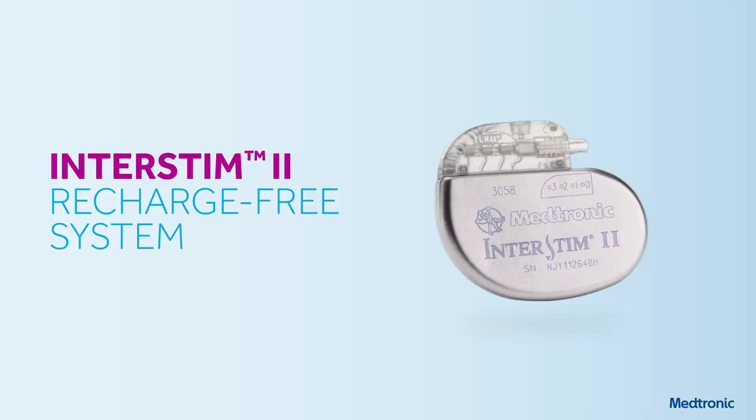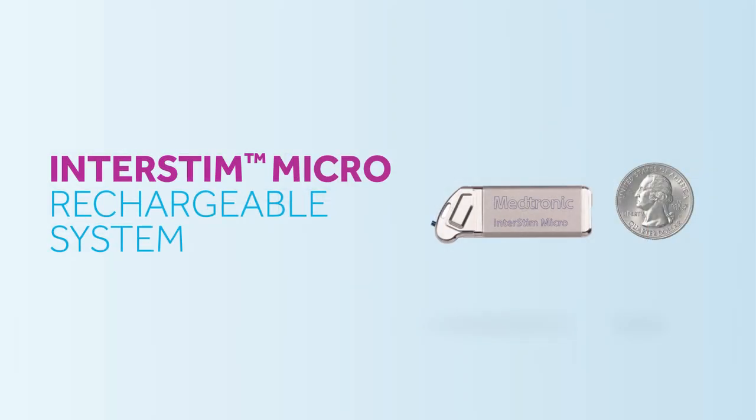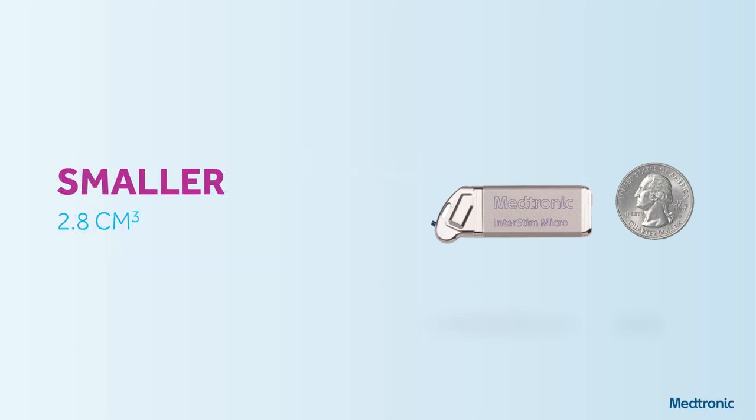Nathan, can you give us some information about the engineering changes? What we've recently released are two completely new systems. Many of the tools and processes are the same, but we've made incremental improvements to improve workflow. There's the Interstim 2 and the new Interstim Micro, which is the smallest neuromodulation device at 2.8 cubic centimeters. There's also impactful overdrive battery technology: the battery experiences no fade at 15 years, patients recharge for 20 minutes once a week, and can recharge from zero to 100% in less than one hour.